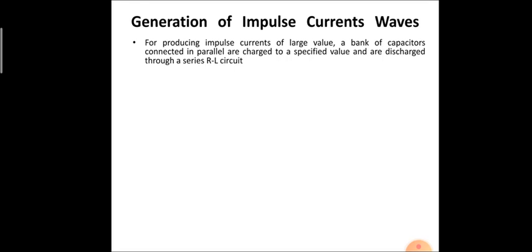So when lightning discharges are involved, having both high voltage impulse and high current impulses, the protective gear we talk about, like surge diverters, have to discharge the lightning currents without damaging the equipment. Therefore, generation of impulse current waveforms of the magnitude of nearly 100 kiloamperes finds application in test work. As I said, it is required for the testing of apparatus which is to be placed outdoors.